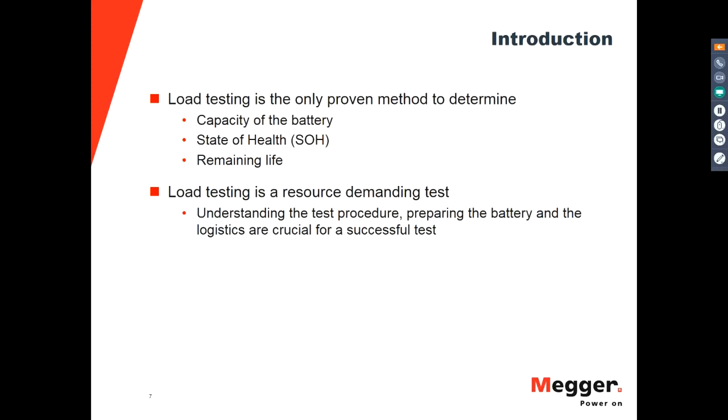However, it is a very demanding test. You require sometimes very big load banks, or you need a lot of time, or you need a lot of preparation, and things can go wrong during the test. And running the test again is not as easy as any other electrical test. So you need to start from scratch, from zero, with the preparation, and well, some things you may not need to do, but it involves a lot of time. So understanding the test procedure, preparing the battery, and logistics are crucial for a successful test. And that's what we're going to talk about today.